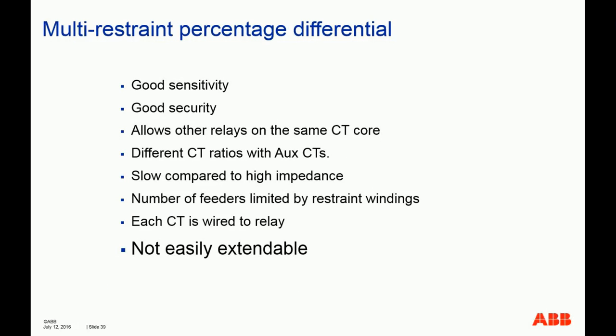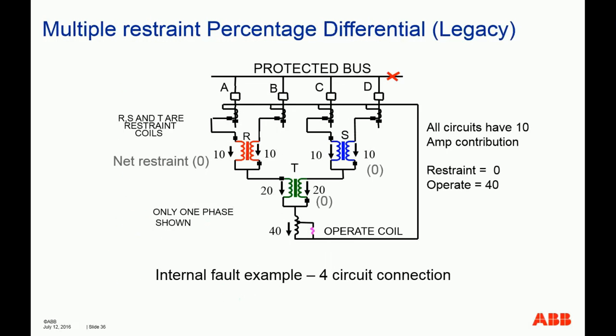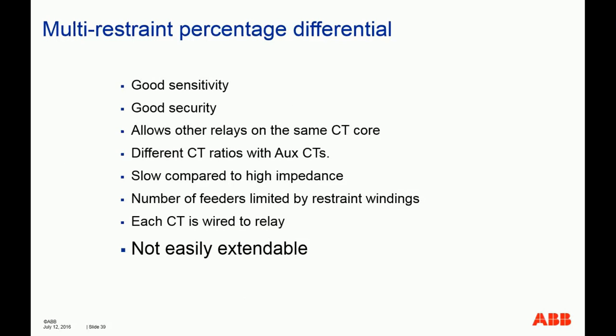So the advantages or conclusions of the multi-restraint percentage differential type of relay are good sensitivity, good security, and it allows other relays on the same CT core. Basically, this is the characteristic of all modern low impedance type of relays. Different CT ratios are handled with auxiliary CTs. The legacy type of relay all require auxiliary CTs to match the CT ratio. It's relatively slower than high impedance relay, and the number of feeders is limited by the restraint windings. As you can see, each connected CT needs to have its own restraint coil. Each CT is wired to the relay, so that also means it's not easily extendable, because the number of feeders is limited by the number of restraint windings.